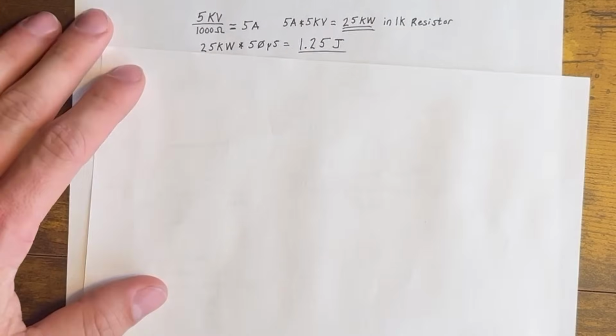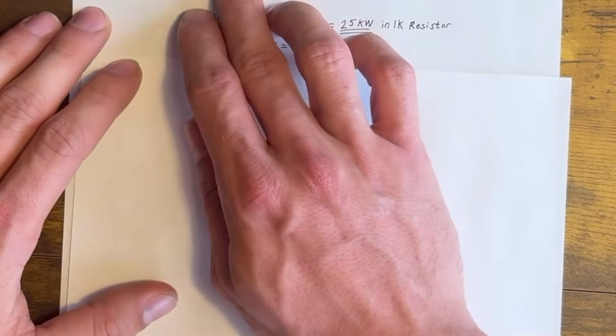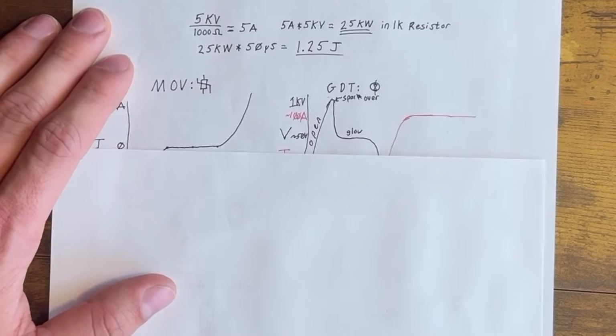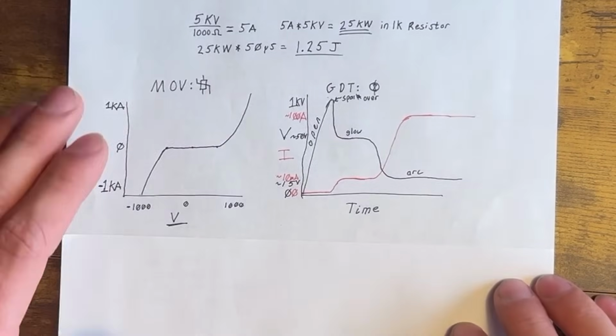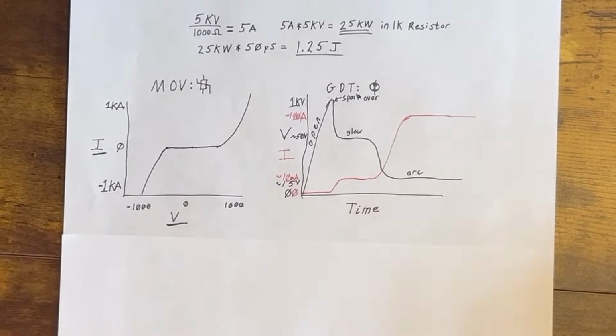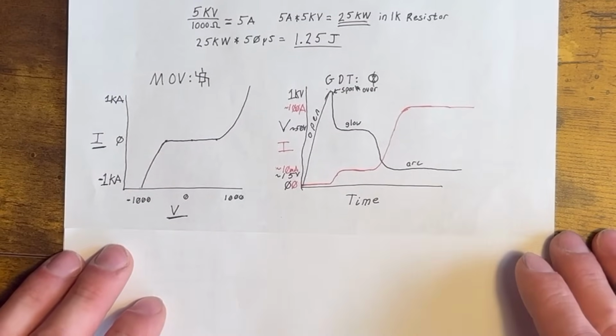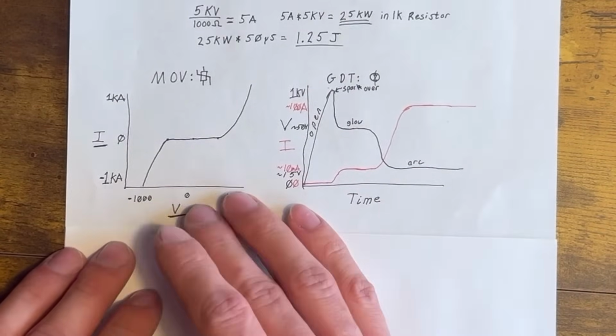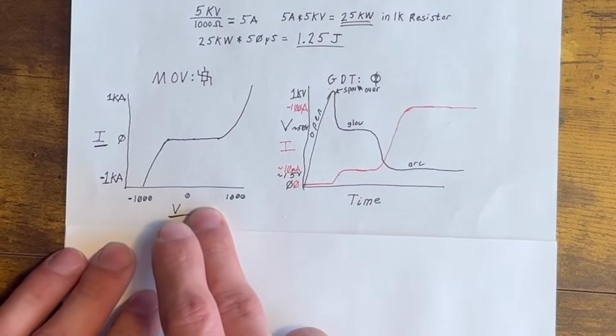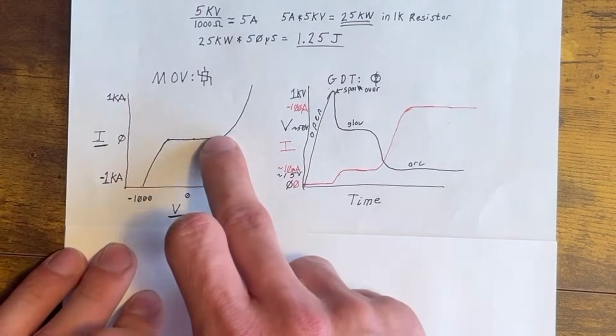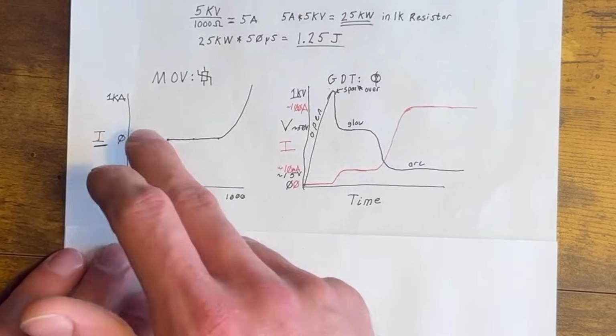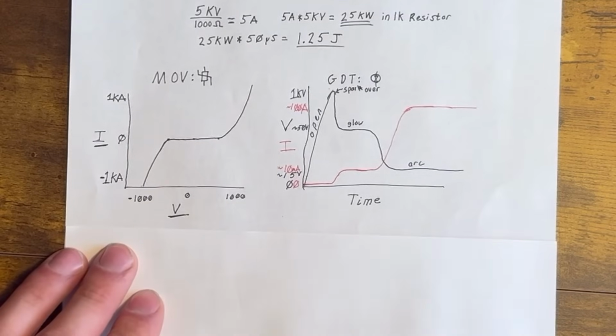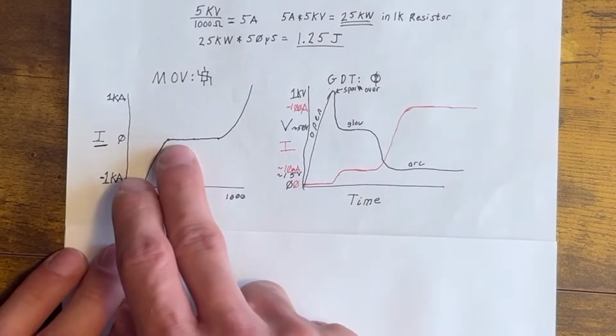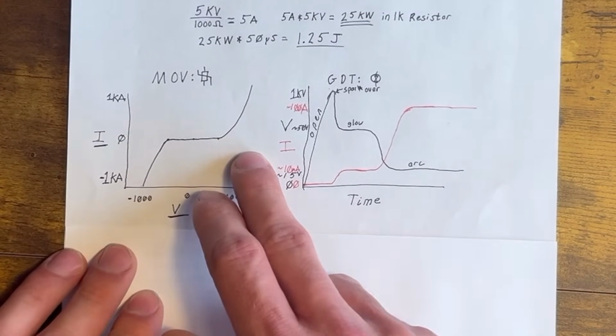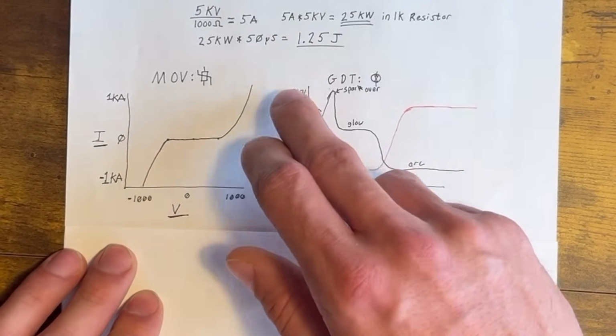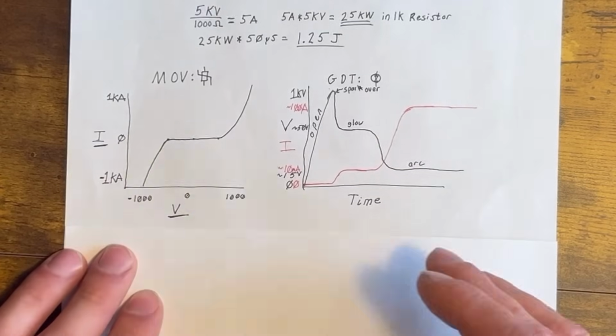To dive a little more in depth on the differences between an MOV and a GDT, gas discharge tube, we'll show some graphs for each of them. It doesn't completely clear it up, but we'll try to explain it as quickly as possible. An MOV is best described by a transfer function. For any voltage you might put across it, you can effectively look up a current in this chart and see how much it will allow to pass through it. Effectively, it passes little current up to some voltage, and then it starts to allow a lot of current flow above that point in positive or negative direction.